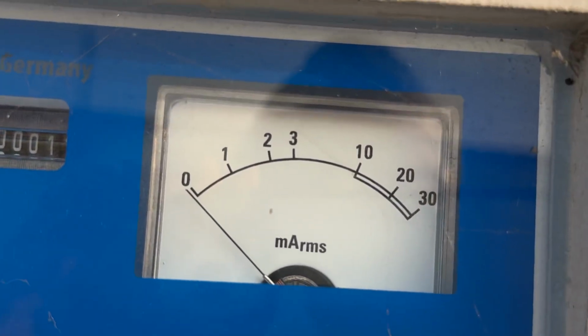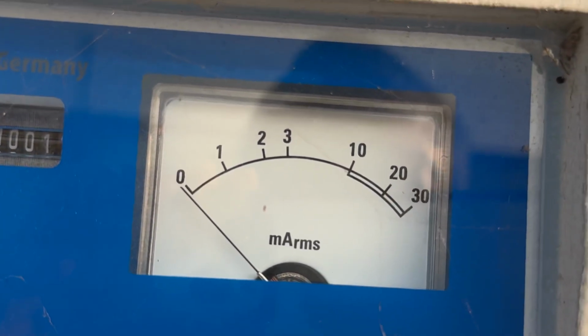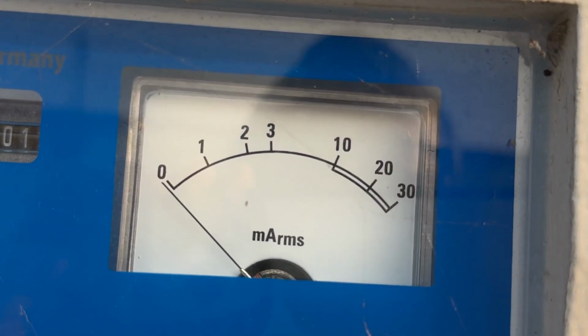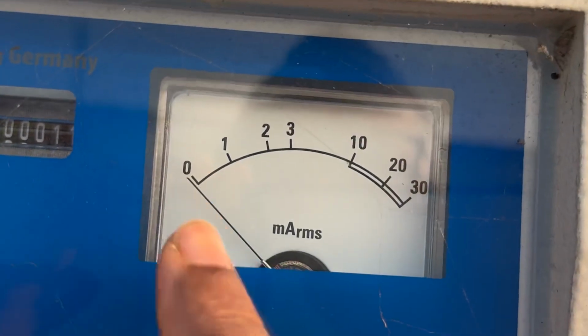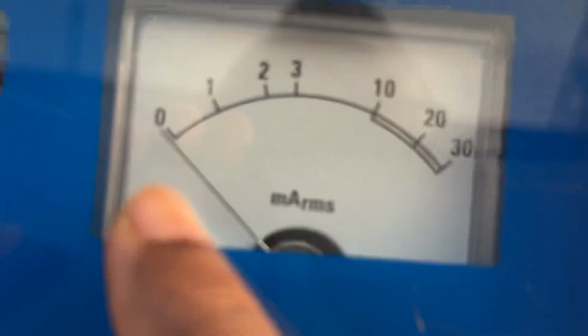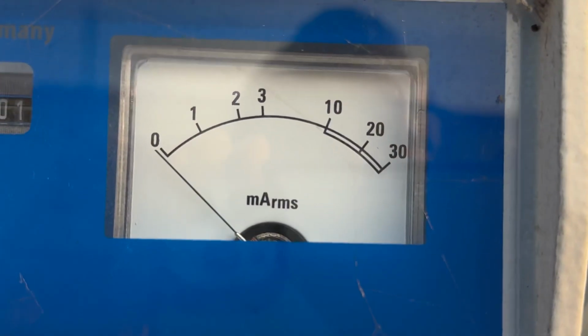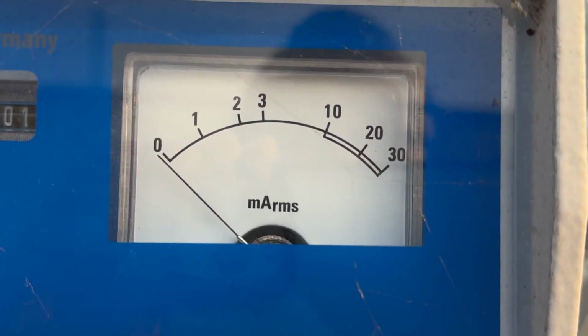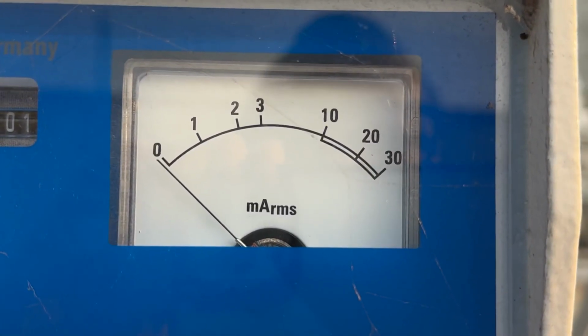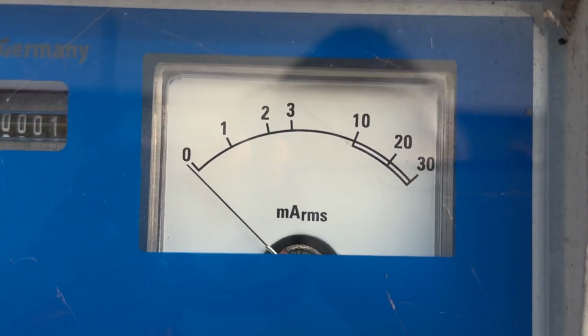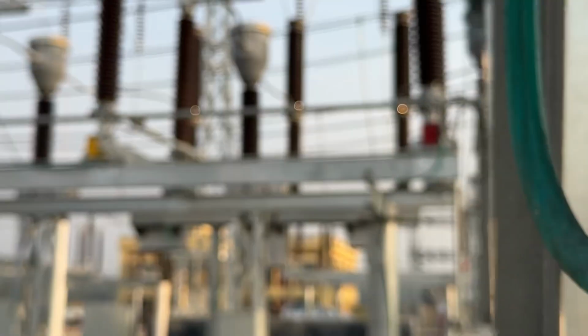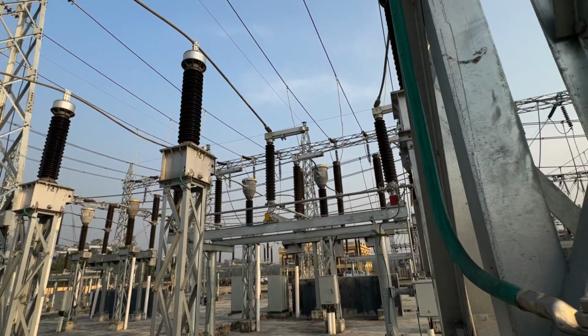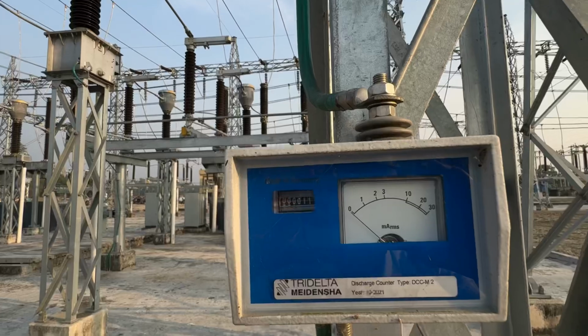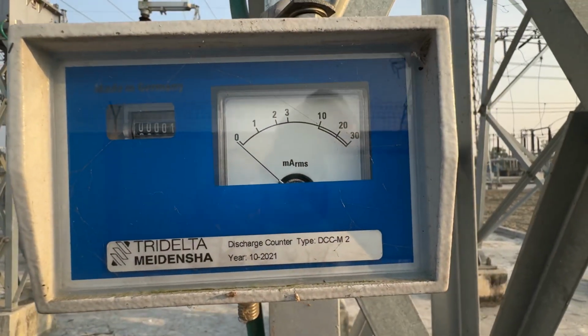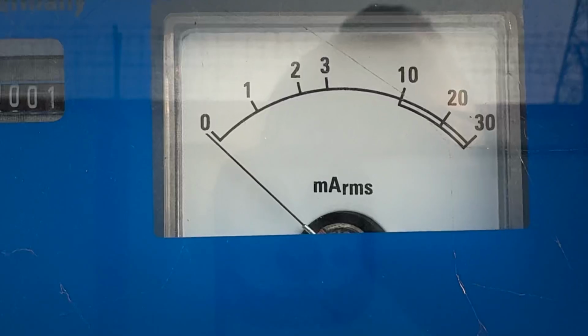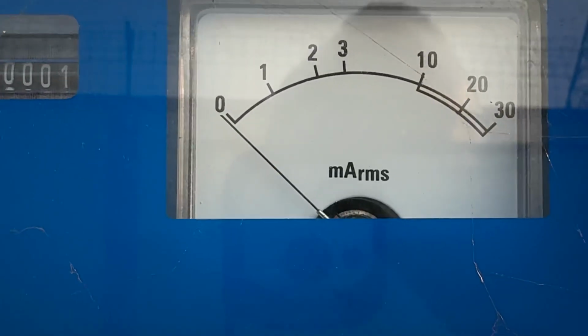At normal condition, some leakage current flows through the lightning arrester. This leakage current is shown by this leakage ammeter. It is an ammeter, but now this circuit is in open condition. There is no voltage here, so no current is showing. Normally the range of this current is 0 to 0.5 milliampere.